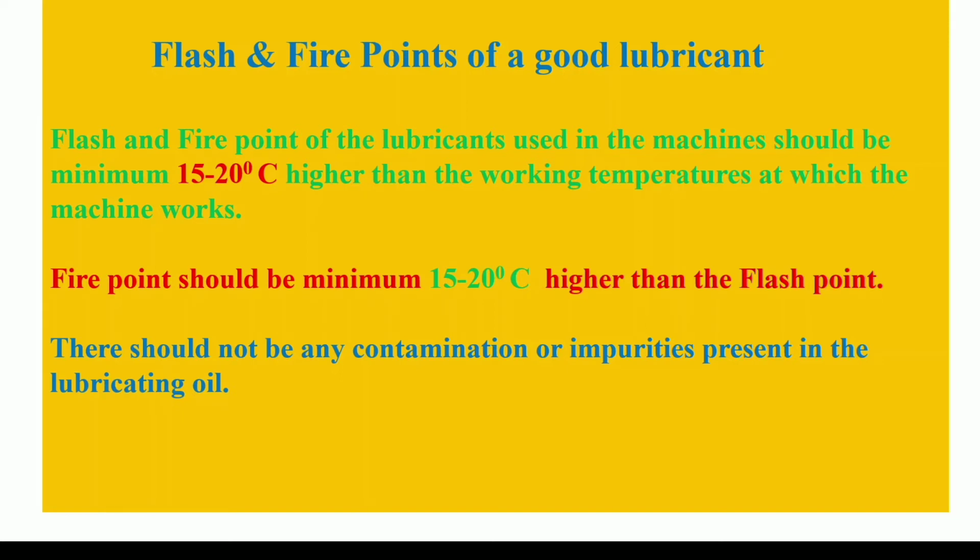Similarly, the flash point should be quite apart from the fire point. That is, there should be a minimum 15 to 20 degrees centigrade difference between the flash and fire point.